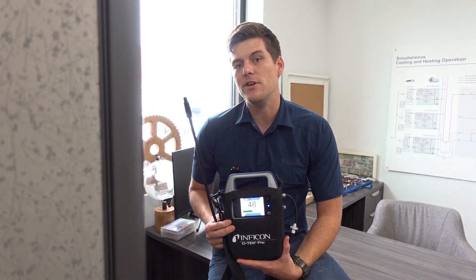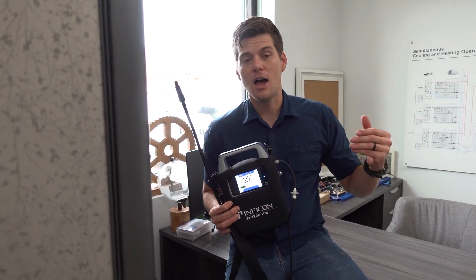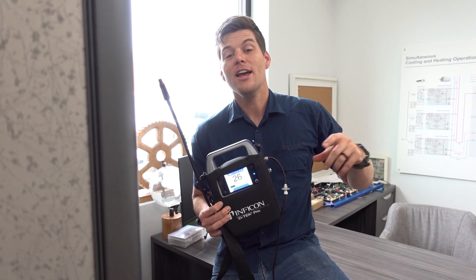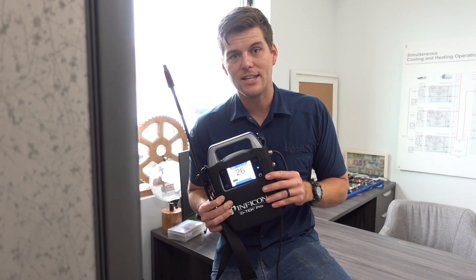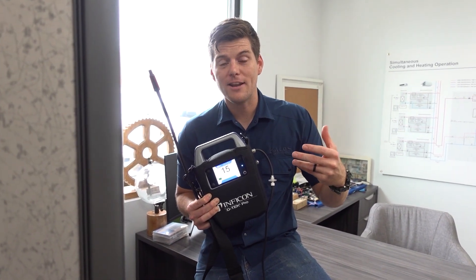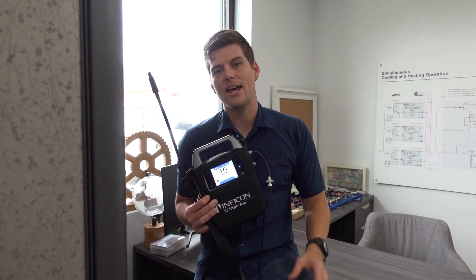There are a few features we haven't talked about yet. One of those is the actual reports that can be generated with the D-TEK Pro. We've been on a journey all day going from warehouse to warehouse, building to building looking for leaks. From starting it to stopping it, we've been able to record that data. The D-TEK Pro has an actual app on your phone that lets you connect to it and pull in the information as it leak detects to create a graph and a chart. They took it a step further and added GPS functionality, so the reports have a GPS timestamp of when and where you did the leak detection. Not only do you get a report with your information and the client's information, but also a chart showing what that leak detection looks like over time — to present to the client and say, here's where we started outside your building, went to motor room one and got nothing, went to motor room two and found exactly where it spiked at the source. Here's the location.